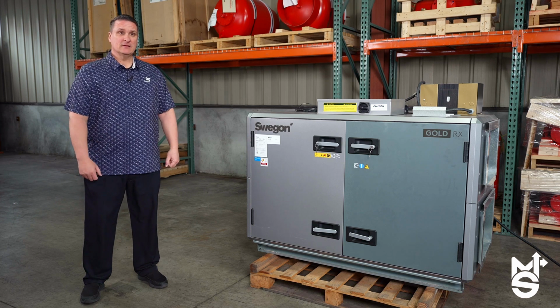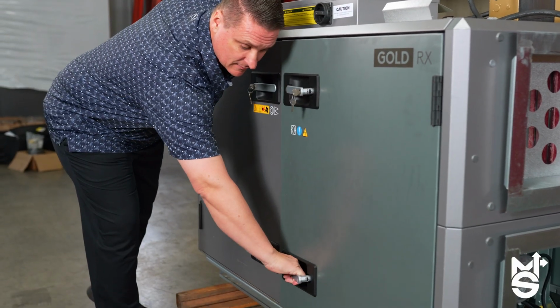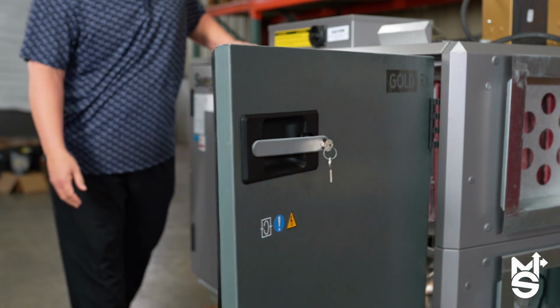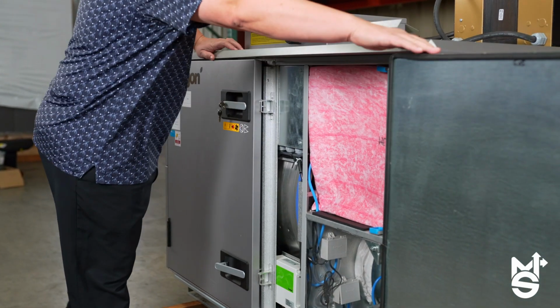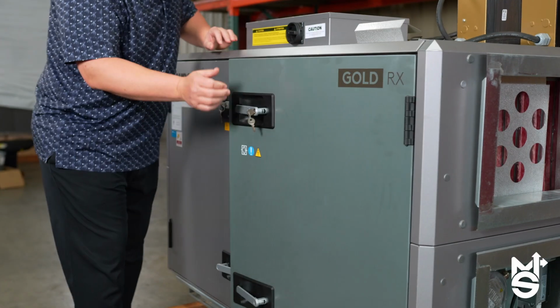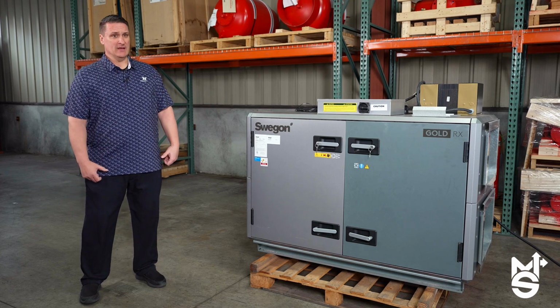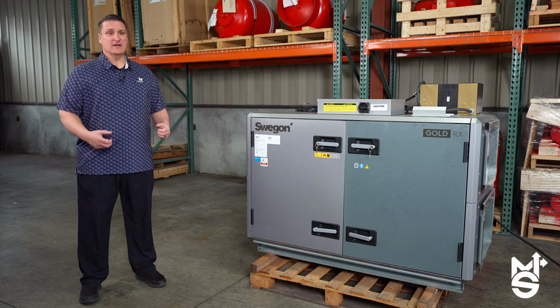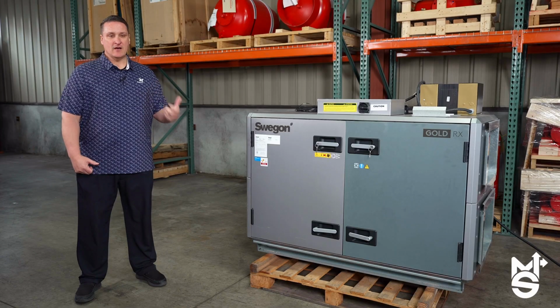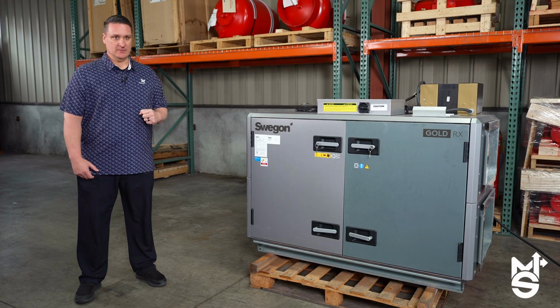Some of the safety benefits of the Swegon ERV are the dual position door handles. One click unlocks the door and releases the pressure. The second click or stage opens the door, allowing access to the internal components. All internal components are on quick mechanical and electrical disconnects, allowing them to be quickly unattached between modules or for removal and service. When looking at the footprint of the Swegon ERV, it is designed to be very compact and extremely quiet. The unit is so acoustically superior, it is commonly installed near occupied areas within a building. It also has extremely low leakage rates.